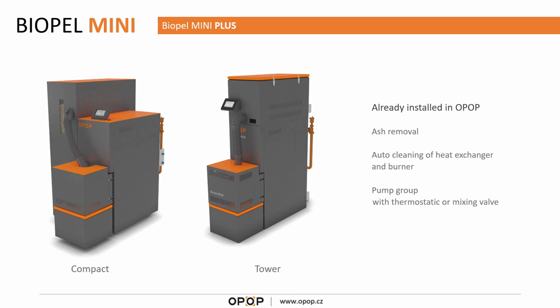Jarka also mentioned Biopel Mini Plus version. So basically all the accessories you already know from the V9 Premium version you can use for Biopel Mini, but all these accessories have improved design. So we still have ash removal system, compressor cleaning for the heat exchanger and burner, and we have also pump group with the mixing or thermostatic valve. But all these accessories are improved to make the operation of these better.